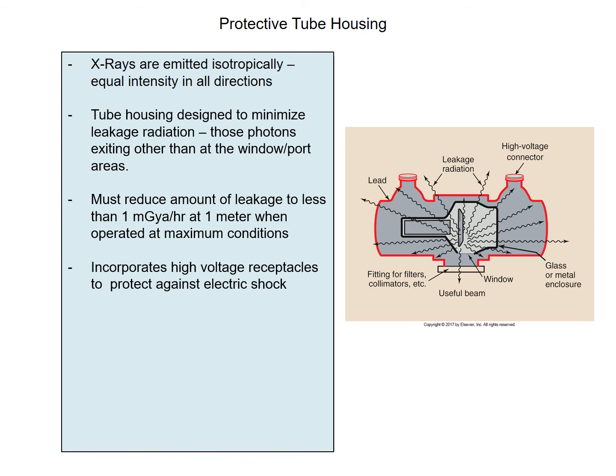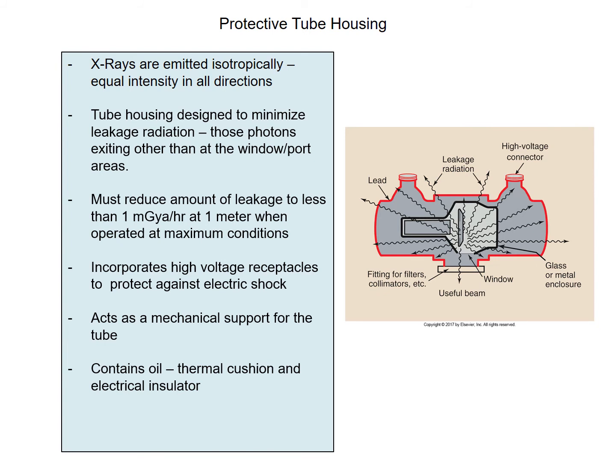The tube housing also incorporates high voltage receptacles to protect against electric shock. You think about it, when you're taking an X-ray, and if we set it up for 120 kVp, what does that mean? 120,000 volts of electricity. So the tube housing has these areas within it that are able to act as receptacles to protect against any electric shock. The tube housing also acts as a mechanical support for the tube itself, and it contains oil, which acts as both a thermal cushion, absorbing a lot of the heat that's being produced, and then an electrical insulator. Remember, we use this dielectric oil that acts as an electrical insulator. And some of your tube housings also have fans built in to aid in cooling as well.